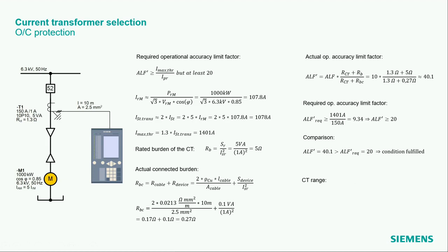Here it's just to mention one basic principle, so an add-on, which does not concern us really for the motor protection, and it is the CT range. That means how big is my maximum short circuit current, which I have here as an internal fault, and does this relay still see that fault current? For this, we can take a simplification. Either you have a full scheme calculation of your maximum short circuit current with a program, or you make an estimation. If you have a transformer upstream of your location, you can get the maximum short circuit current behind the transformer by dividing the nominal current of the transformer by USC, the relative short circuit voltage, which has values like 0.1, 10%, 5%, 15%, something in that range. And here it is expressed with the power of the transformer, so you get a certain value.